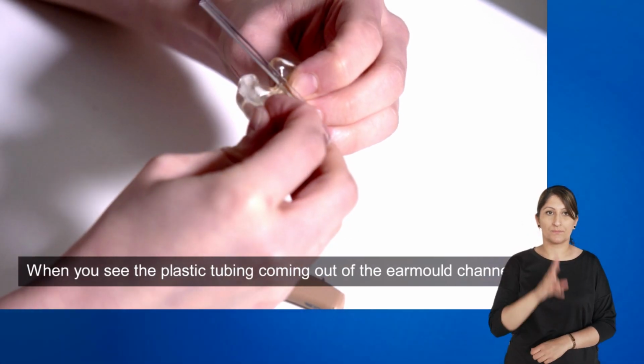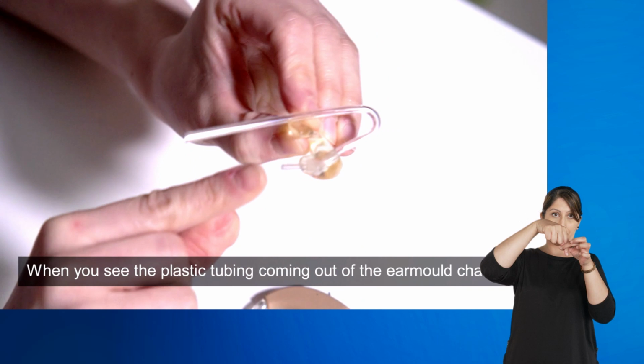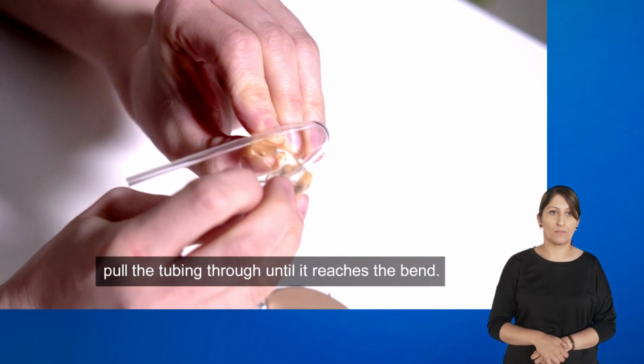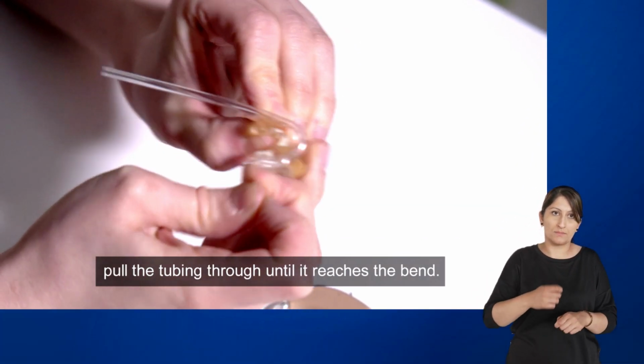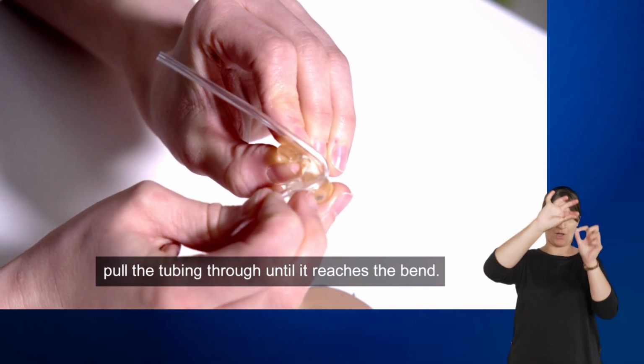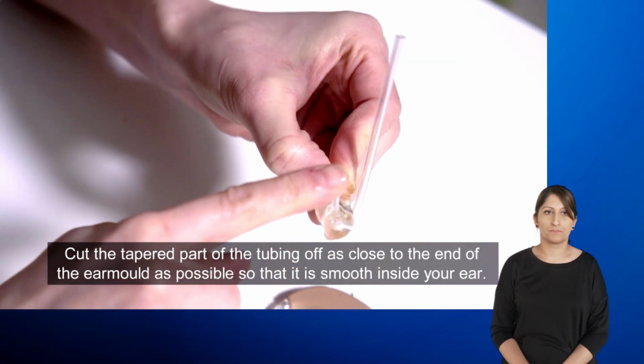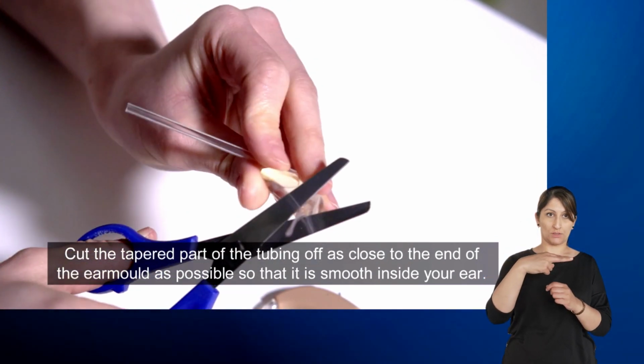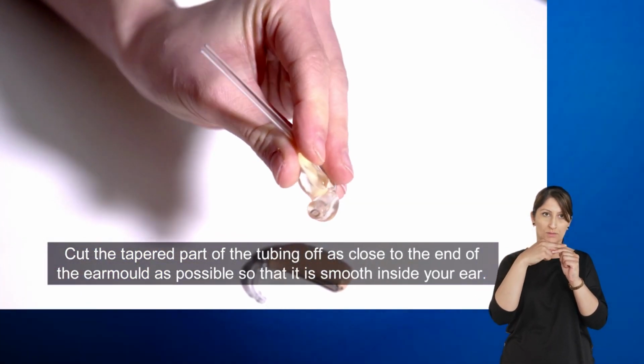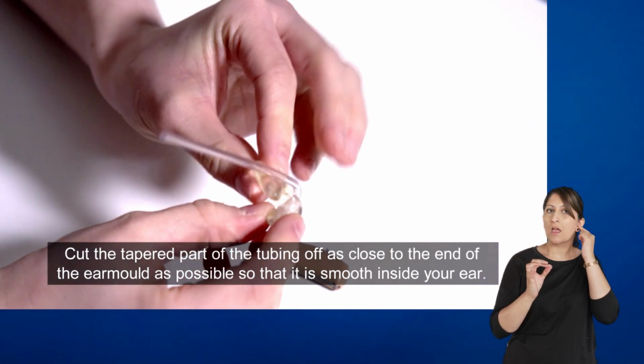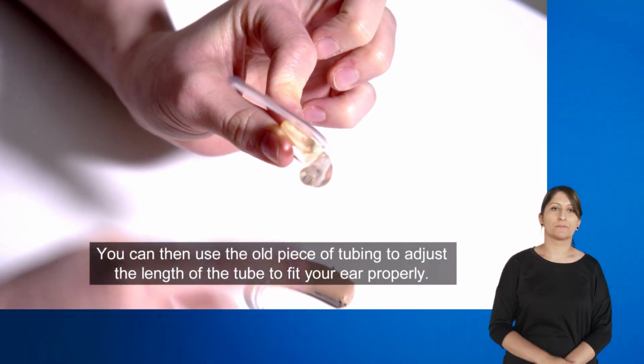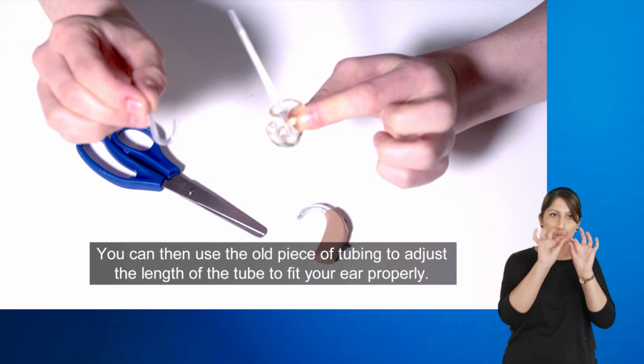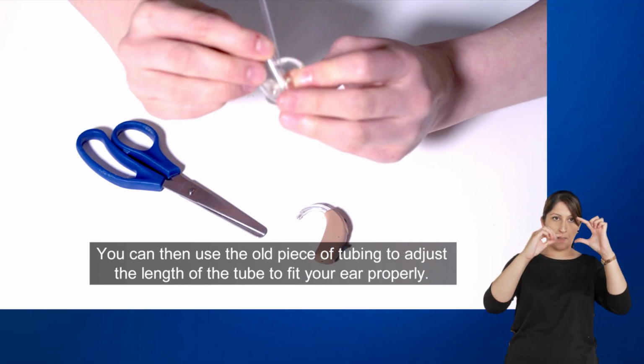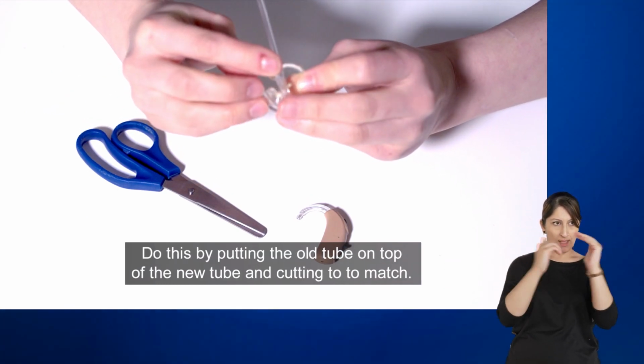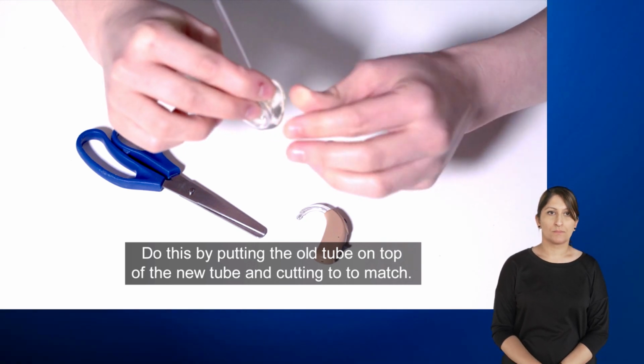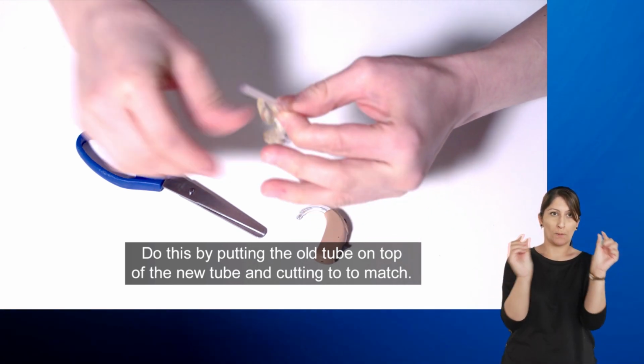When you see the plastic tubing coming out of the ear mold channel, pull the tubing through until it reaches the bend. Cut the tapered part of the tubing off as close to the end of the ear mold as possible so that it is smooth inside your ear. You can then use the old piece of tubing to adjust the length of the tube to fit your ear properly. Do this by putting the old tube on top of the new tube and cutting it to match.